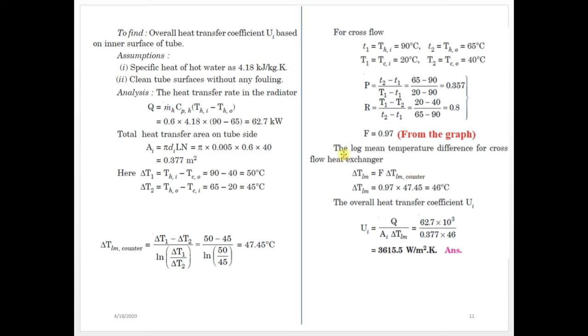The overall heat transfer coefficient Ui is equal to Q divided by Ai × delta TLM. Substituting all values, we get Ui = 3615 W/m²K. This confirms that the correction factor is required for heat exchangers other than parallel flow and counter flow types. The log mean temperature difference for shell and tube and cross flow heat exchangers must be corrected using factor F.